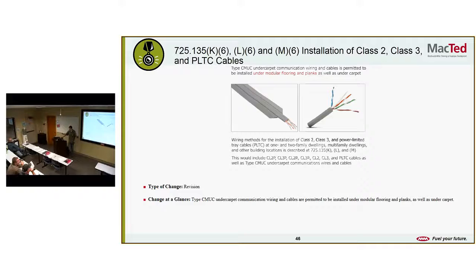Installation of Class 2, Class 3, and PLTC cables. This is under carpet communication wiring and cables. It is now permitted to be installed under modular flooring and planks as well as carpets. So this looks like some interesting stuff. Cat 5 maybe, some kind of communications cable. You can run it underneath your carpeting or your wood floors, your modular floors, snap together. Speaker wire, good call, I like it. Okay, any questions on PLTC cables? Nothing? Sure? It was the last slide.